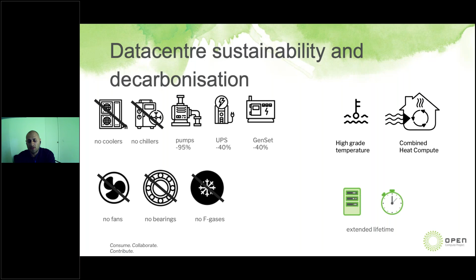So a data center with immersion servers doesn't need equipment like air conditioners, chillers, cooling towers. At the same time, it requires smaller UPSs, gensets, and less white space, which gives the chance to reduce embodied carbon footprint by up to 50%. The high-temperature outlet liquid allows heating up water for heating and tap water systems, with valuable goods production. No need to invest in heat pumps, which provides instant cost reduction without additional support from any other institutes. Exclude all fans in servers, bearings, and chiller refrigerants without evaporative cooling.